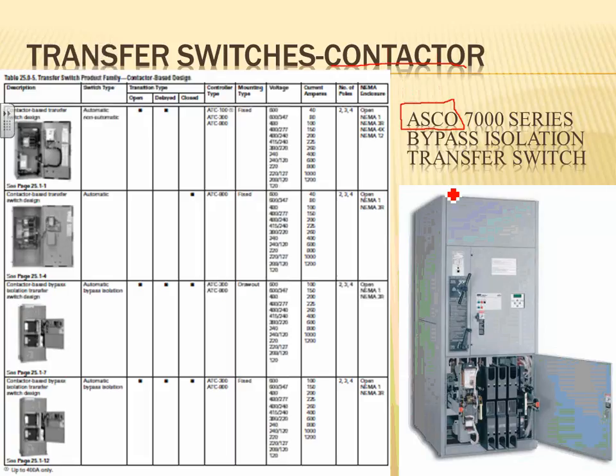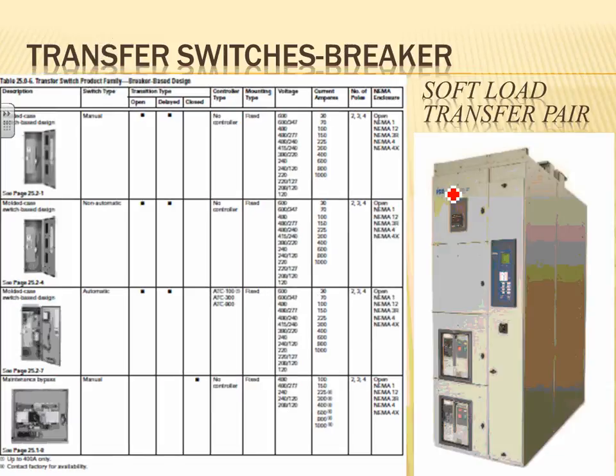So they use the technology of contactors to open and close and transfer your power. That's one technology. The other technology is to use circuit breakers. The bigger sizes, bigger auto transfer switches, start using electronic circuit breakers, where it's almost like paralleling. You close and open these circuit breakers.